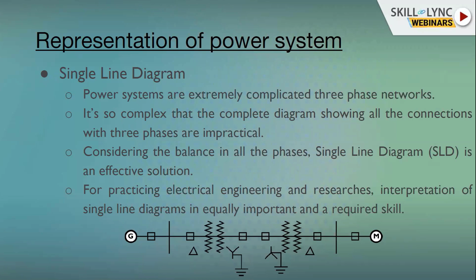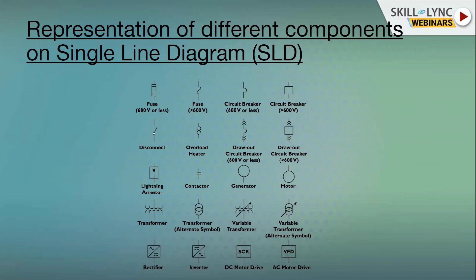These are a few symbols of some components of the power system network. In the beginning we can see fuses. There are multiple representations for the fuse, multiple representations for circuit breakers, then disconnect switches, lightning arresters, contactors, generators and motors, transformers, variable transformers, and inverters, rectifiers or motor drives. One point should be noted here: there are no universally accepted notations for representing these power system components. In some particular country they may use different notations for a transformer, transmission line, load or generator, while in some other company or country they use different notations. That is the beauty of the single line diagram; it is quite flexible and depends completely upon the utility or the service provider.